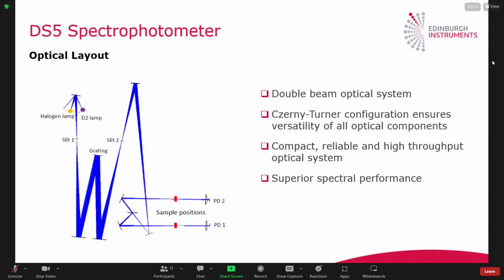Here you can see the optical layout of the DS5. It has a double beam optical system. The beam will pass through both the sample holder and the reference holder. And it has a Czerny-Turner configuration that allows versatility of all the optical components, and it has a compact design of the optical system, and it can provide you a superior spectral performance. Any questions?